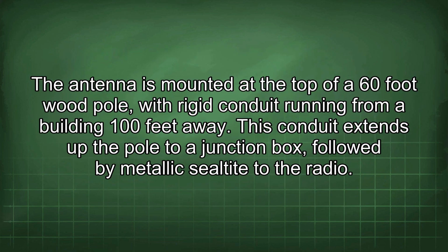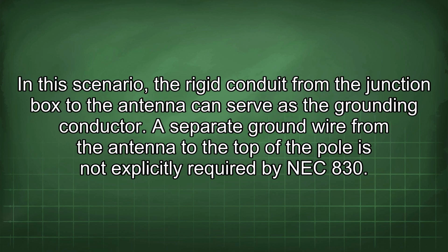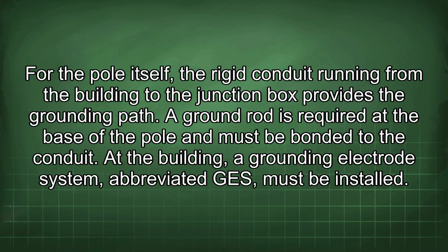Firstly, let's consider the application involving a wood pole. The antenna is mounted at the top of a 60-foot wood pole, with rigid conduit running from a building 100 feet away. This conduit extends up the pole to a junction box, followed by metallic sealtite to the radio. In this scenario, the rigid conduit from the junction box to the antenna can serve as the grounding conductor. A separate ground wire from the antenna to the top of the pole is not explicitly required by NEC 830. For the pole itself, the rigid conduit running from the building to the junction box provides the grounding path.